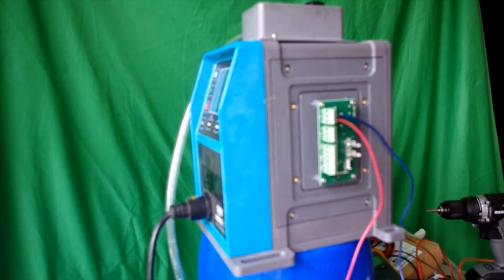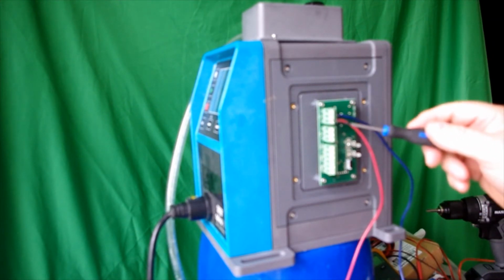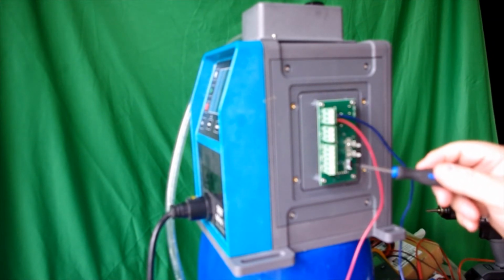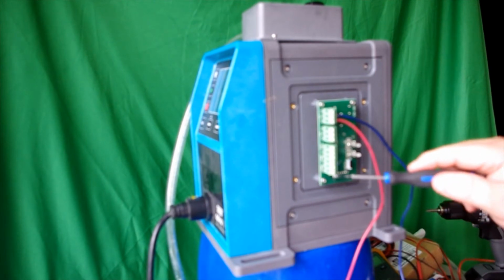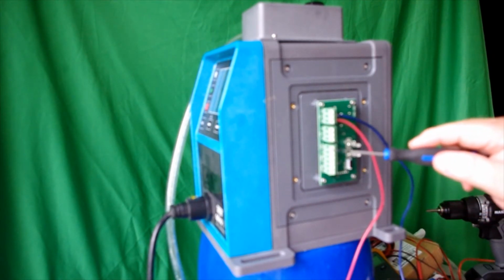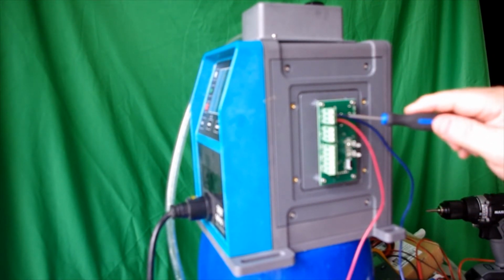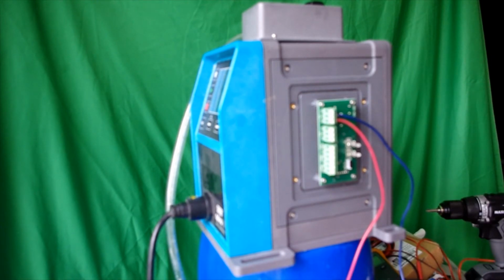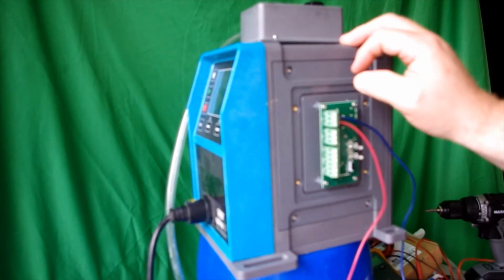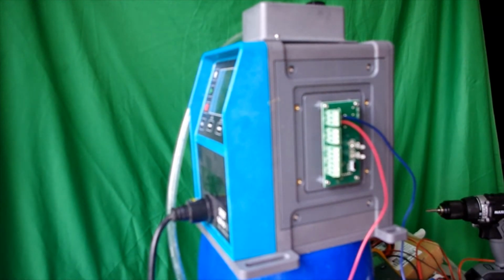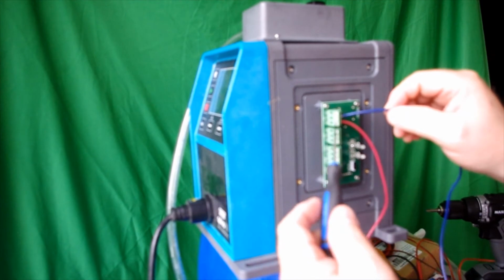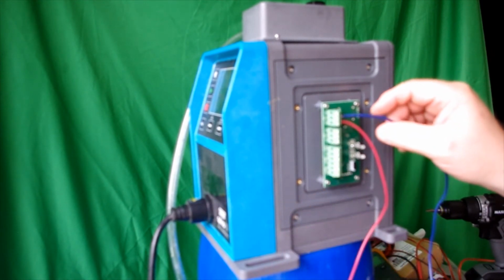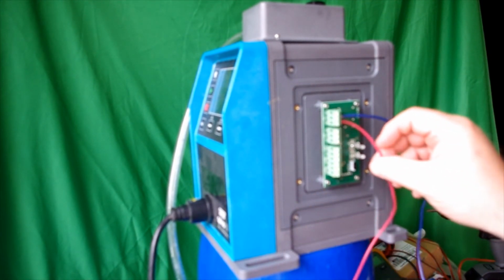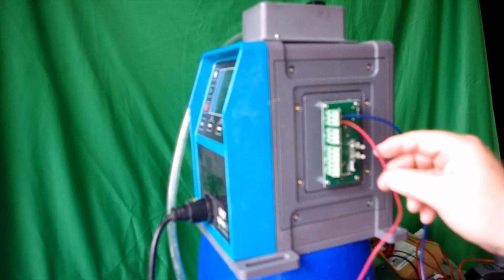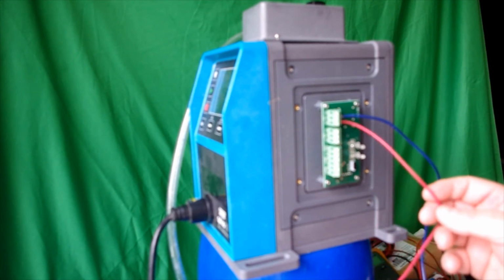Now what you see here is your wiring module for the qdos 60 universal 24 volt. Here is your analog controls. Here is your relay 2, and this is your relay 1. So in this particular case, I wired up this alarm so that when it trips, it closes the contact. So the term is called normally open. So I wired the ground wire right here, the 3rd terminal, to ground. The normally open contact went to the positive of the contact going to your SCADA system.